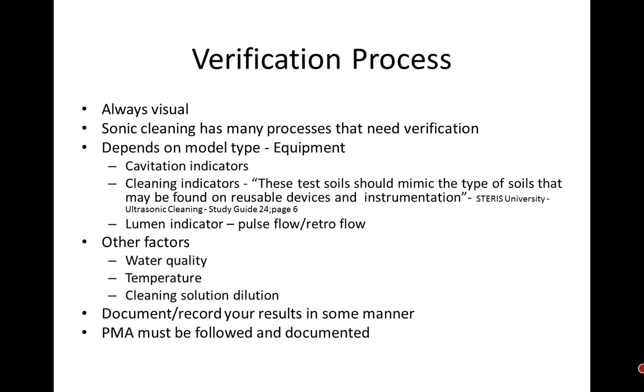Sonic cleaning has many processes that need verification, and it depends on your model and type. They definitely have to have their cavitation checked separately, because cavitation and cleaning, while it's happening there, do not always take place. You want to make sure cavitation is taking place, and you want to make sure that you're checking the cleaning function. And I've taken this quote from the STERIS study guide on page 6. It says, test soil should mimic the type of soil that may be found on reusable medical devices and instruments. So when you're looking for a cleaning indicator to see if you're removing your soil from the device, or what you're using to test, to make sure that surrogate device, hopefully the device you're using is going to mimic the soil you're trying to get off.